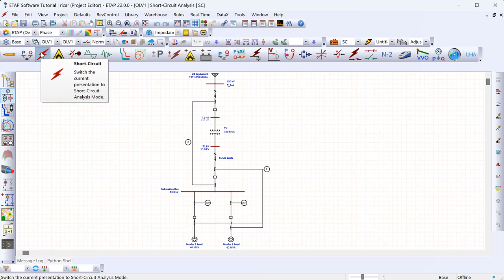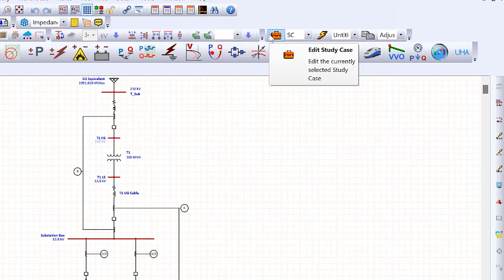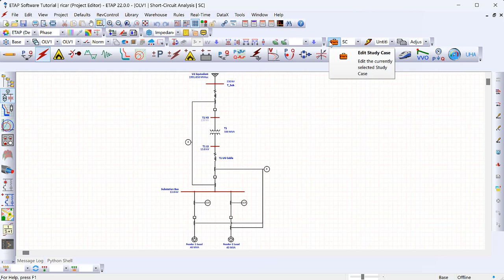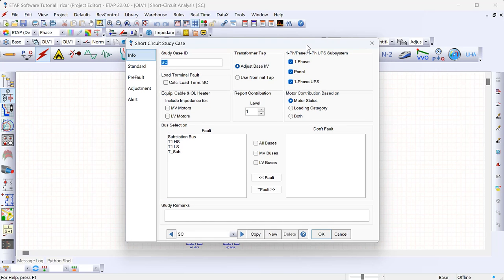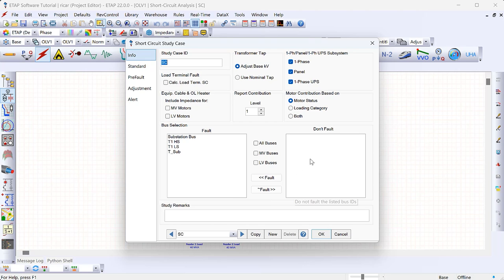The first thing I want to do is go to the study case, which is where we define how to run short circuit studies — which buses to fault and what standards to use. Clicking on that opens up this window, where you have a list of buses in your system that you're going to fault. In our case I want to fault all the buses, so I've moved everything over to the left where it says 'fault'. If we didn't want to fault some buses, we can move them to the right side.